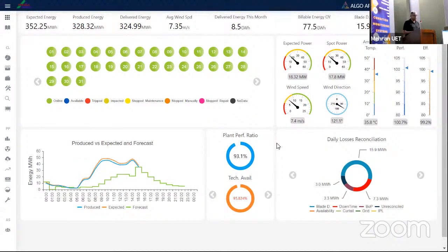Those loop cables arrive at a substation where there are more energy meters. If you take the difference between the energy produced at the foot of the turbine and what's received at the substation, you can calculate how much energy was lost in the cables and how much was lost in the step-up transformers at the foot of the turbine.